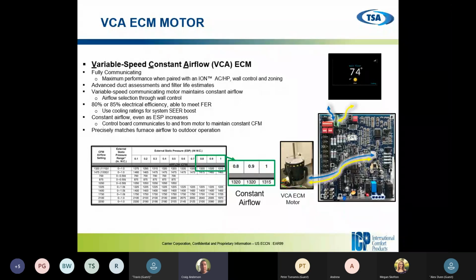So things to look at when you're out there selling now, because these motors work a lot differently than a standard speeded motor: we need to look at static pressure, duct sizing, and the filters that we're putting in it. So be very mindful when you're out there doing service, and we'll go over some static pressure readings later on. So this one's fully communicating, the 97 and 96 communicating furnaces.